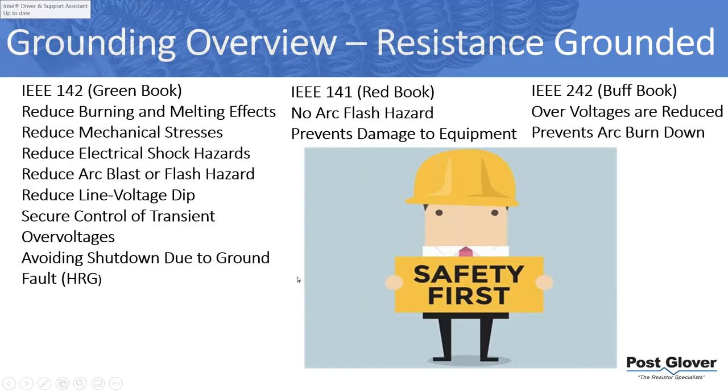Once again, you're not getting rid of your phase-to-phase issues, your three-phase issues. So don't get me wrong, we're not eliminating the requirement for PPE. We're not getting rid of all your arc flash. I wish we would, because then not only would the world be a lot safer place, but we would also be on an island somewhere on the beach, because we'd be retired, because everybody in the world would be using high resistance ground. And they ought to, in my opinion. Maybe I'm biased, but they should be. It's a lot more safe.